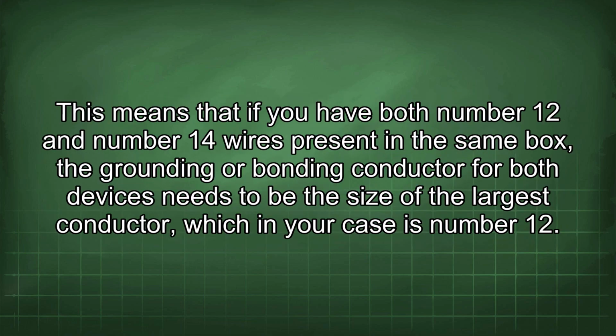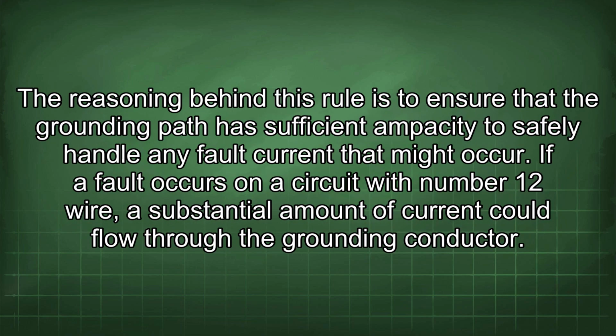This means that if you have both number 12 and number 14 wires present in the same box, the grounding or bonding conductor for both devices needs to be the size of the largest conductor, which in your case is number 12. The reasoning behind this rule is to ensure that the grounding path has sufficient ampacity to safely handle any fault current that might occur.